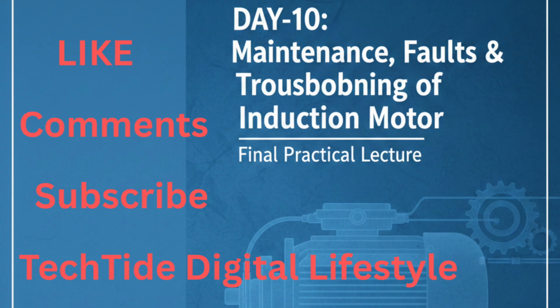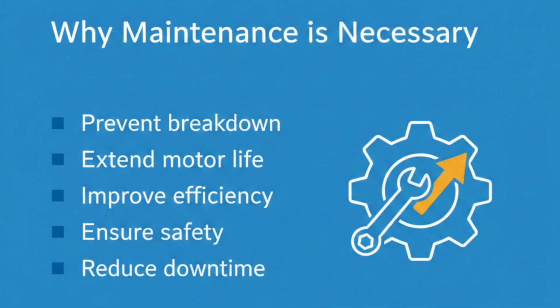Let us begin with the importance of maintenance. Induction motors run continuously for many hours and are exposed to dust, humidity, vibration, temperature rise, and electrical stresses. Over time, these factors degrade insulation, dry out lubricants, and loosen mechanical parts. Regular maintenance prevents sudden breakdowns, improves reliability, saves repair costs, and ensures personnel safety. A properly maintained motor can run efficiently for decades.